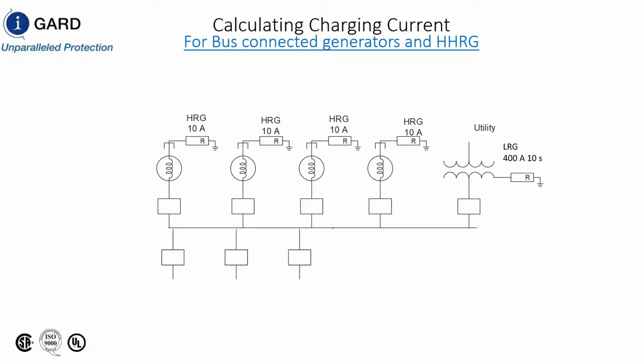So there are two things that you have to consider when you're using a hybrid high resistance grounding system. If the utility is always going to be connected to the system, you could have a 400 amp 10 second resistor connected to the transformer and then a 10 amp resistor connected to each generator. As long as you don't island, this will do. If you're islanding, then the issue is you will not have enough ground return current to overcome the capacitive charging current of your system. So this is why a zigzag transformer on the bus will do. Now you're able to use the utility or the generators or both. In the previous example, this one, when we had the 400 amp resistor here, you always had to have the utility connected to the system.